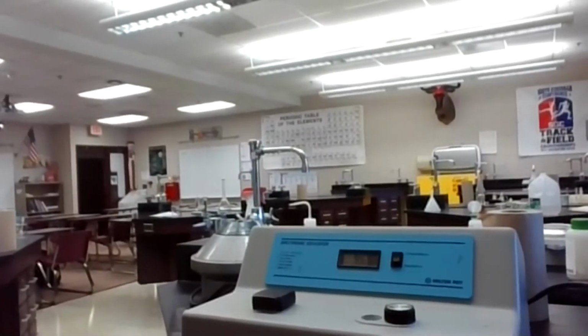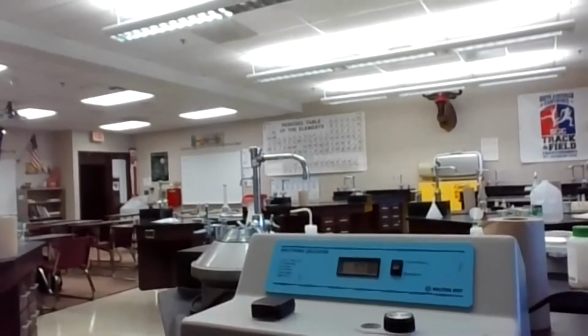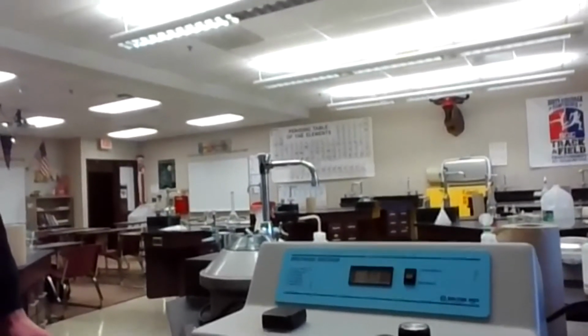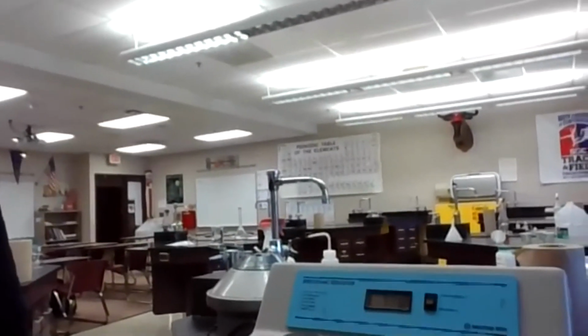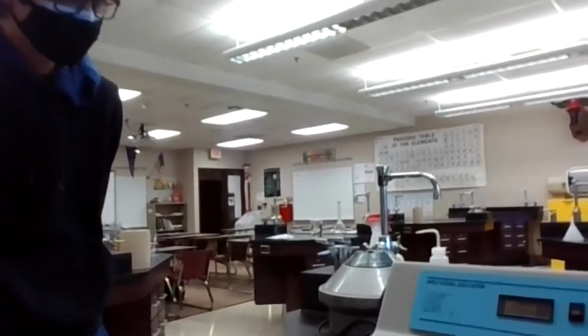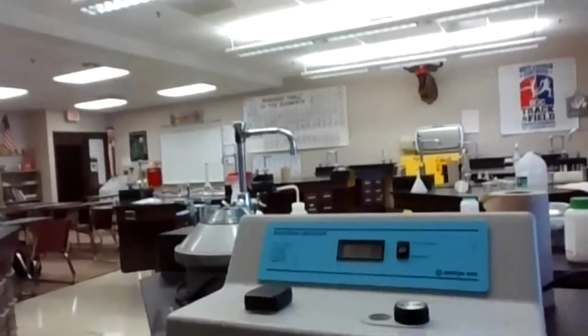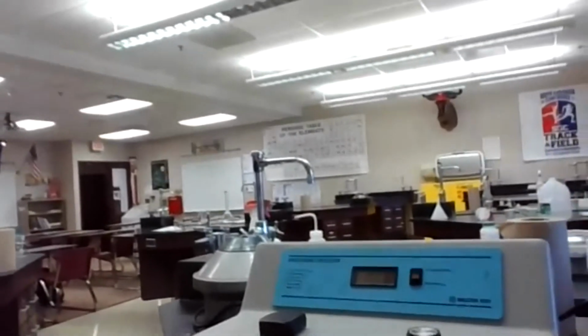And this is pretty fine tuning. I think we've got to go the other way. There you go. And again, you might get 99 or 100. That's pretty good if it's oscillating back and forth right there. So that is going to be our transmittance is 100%. Okay, just do a little tweak here. Watch, I'm going to screw it up here. I'm going the wrong way. Okay, our transmittance is 100%. That would be 0% absorbance. We're going to do things in transmittance and then do a conversion to absorbance.